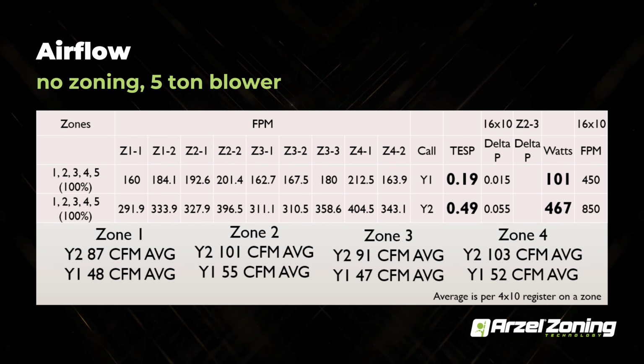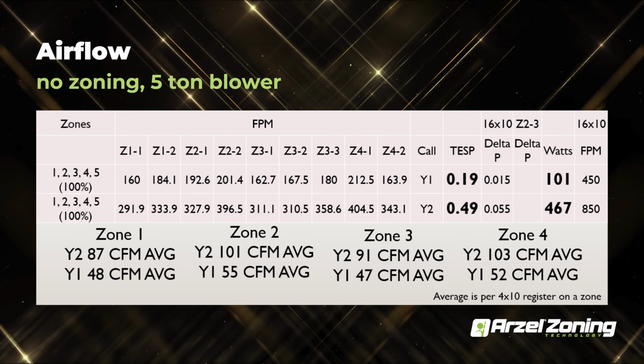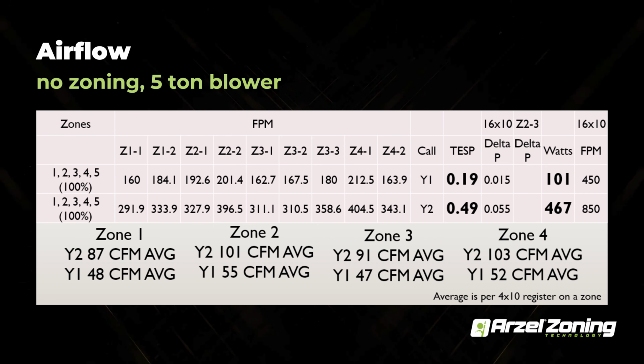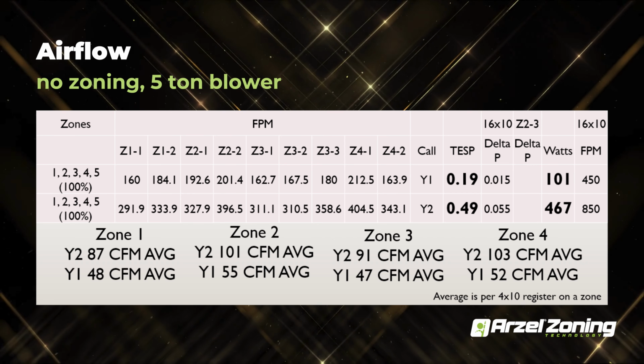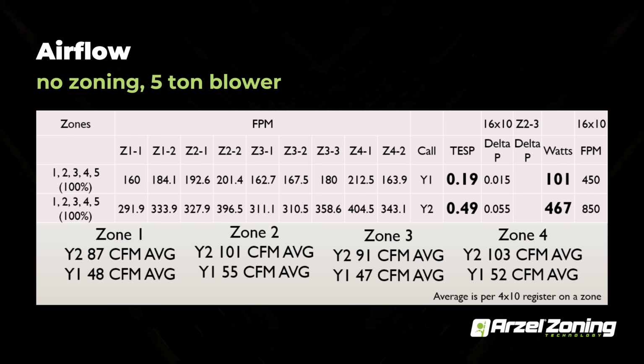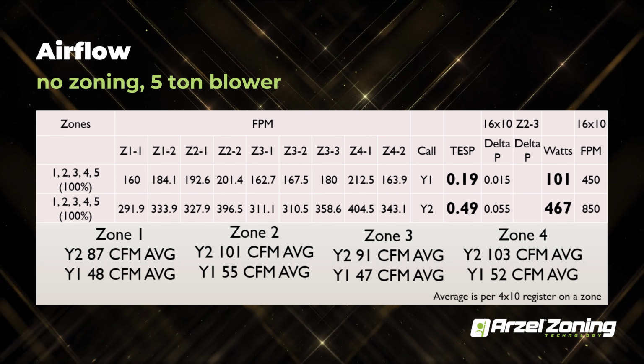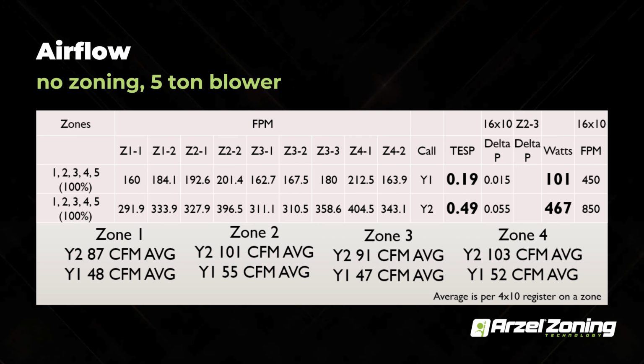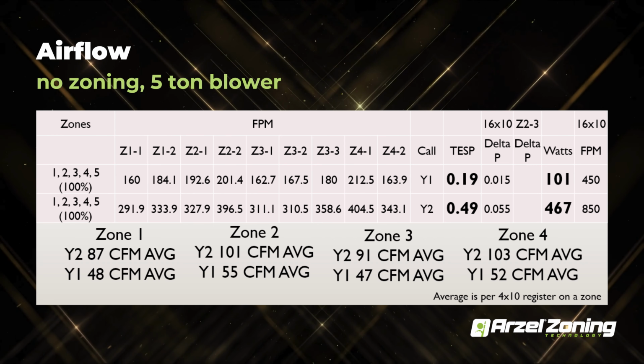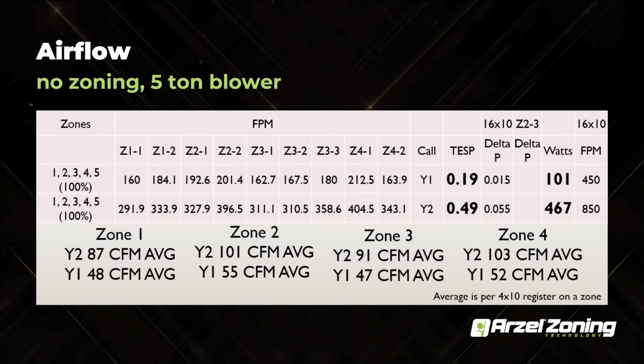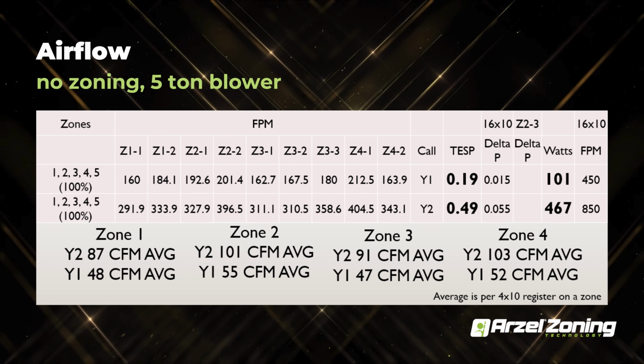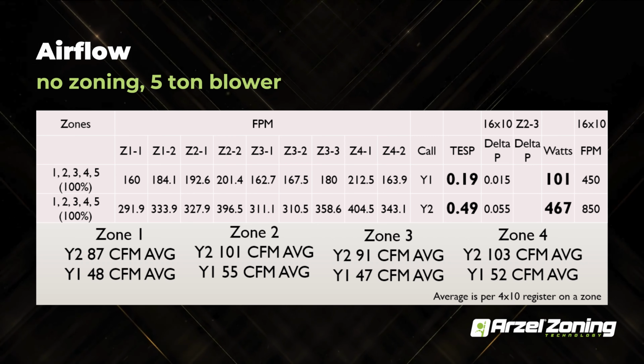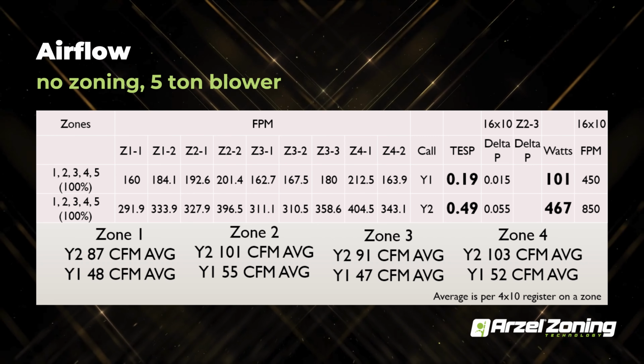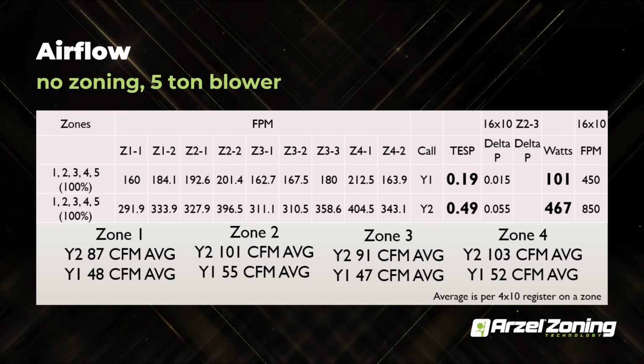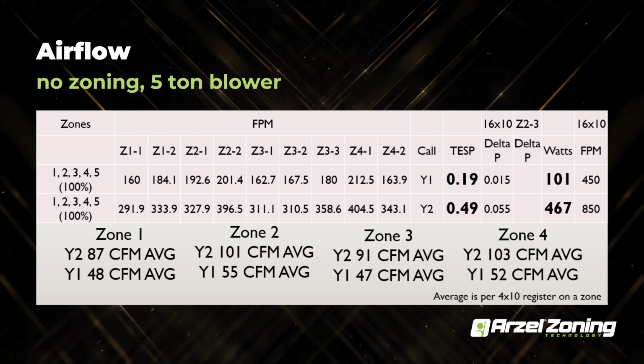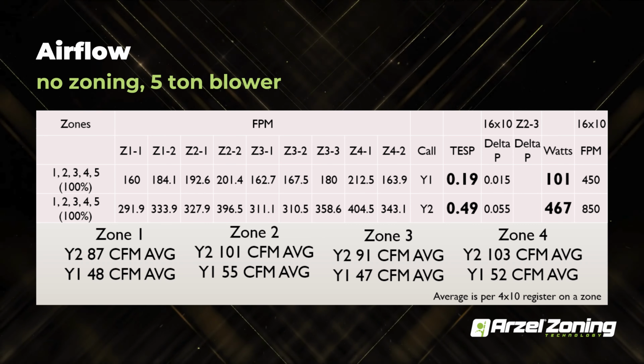And these are just some static readings that we were doing. So on your typical 5-ton blower, non-zone system, and these are our test results back there. On a Y1 output, we were able to maintain a 0.19 total external static pressure. And then when we exceeded to our second stage output for cooling, we were able to maintain a 0.49. And this is without zoning completely, so this is all the ductwork open up 100%. So this is what you would look for before you start zoning a piece of equipment. This is a pretty well balanced piece of equipment. It's maintaining its static where the equipment manufacturer wants it. So we know if we had zoning, we're not going to push this equipment past the limit.